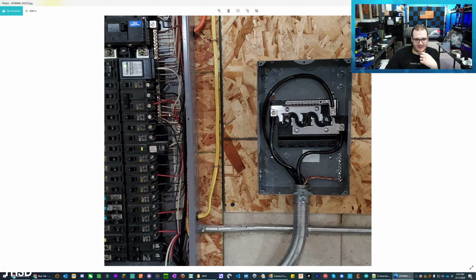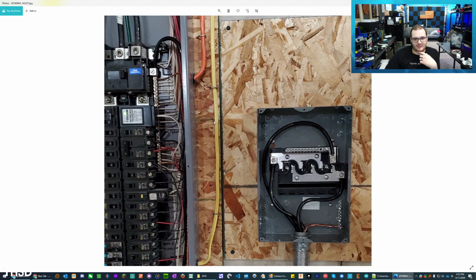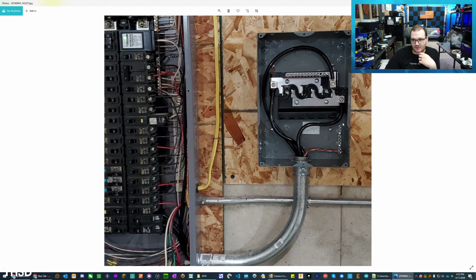You can see it here. Just so you're aware, in your main panel, the neutral should be bonded to the ground. In sub panels, the neutral and ground should never be bonded, period.